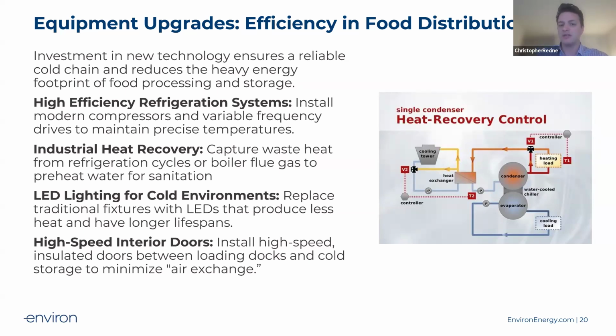And then lastly, high-speed doors. We see a lot of times dock doors, especially in refrigeration areas, where the doors are just wide open, especially if you're in the middle of production on first shift. I can't tell you how many times we've walked around a facility and there have been doors open all over, even trucks wide open. And you have so much cold air going out the door, literally. There is technology now that will automate that, using sensor technology to open and close the door whenever needed. Usually it's rubber, so it takes safety into account as well. That can save significant energy.